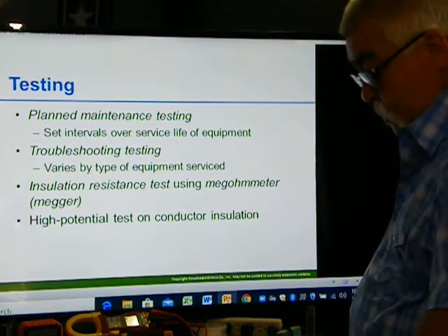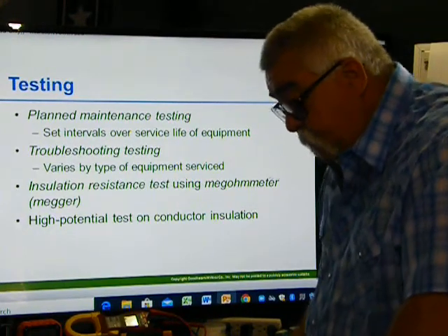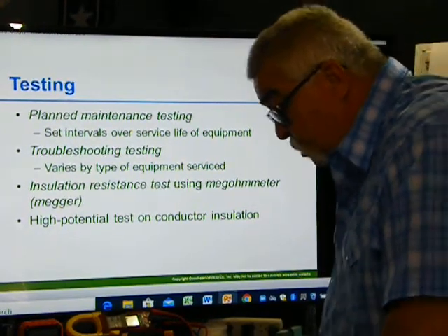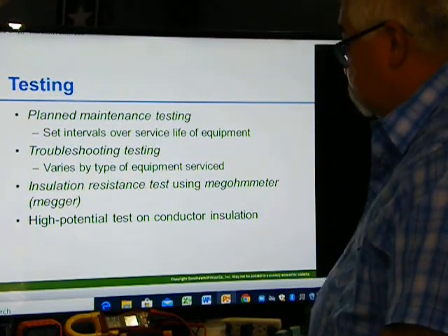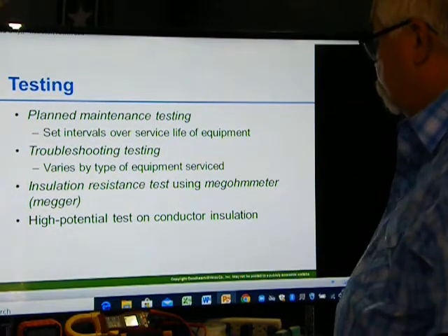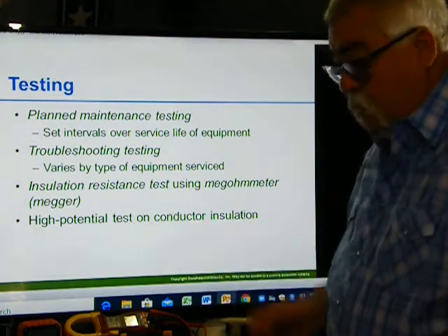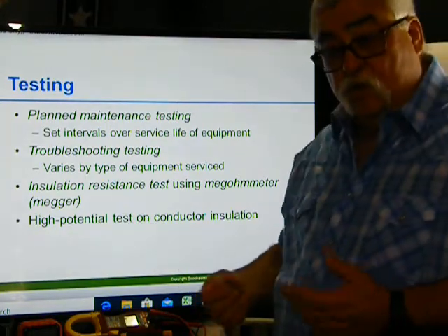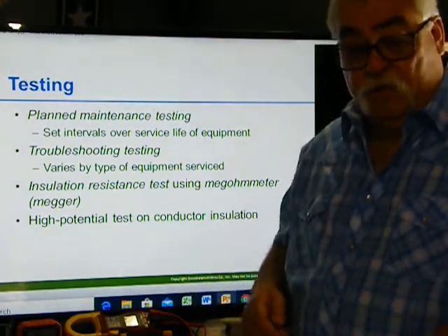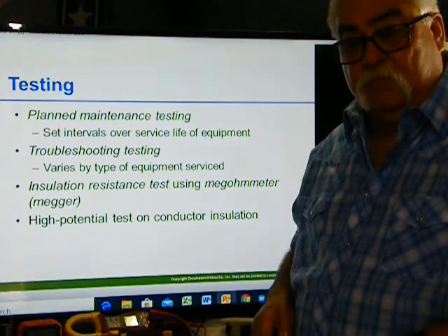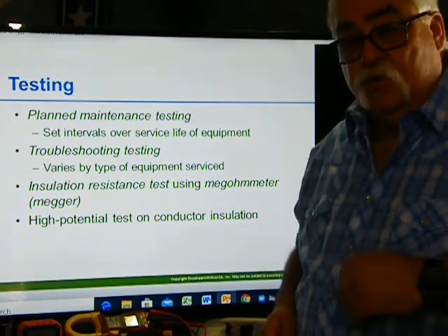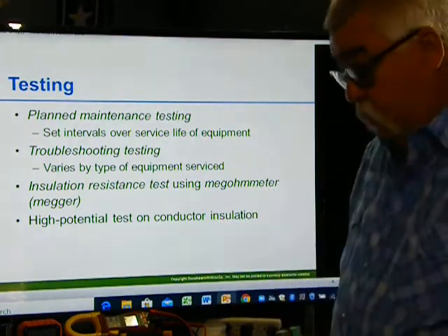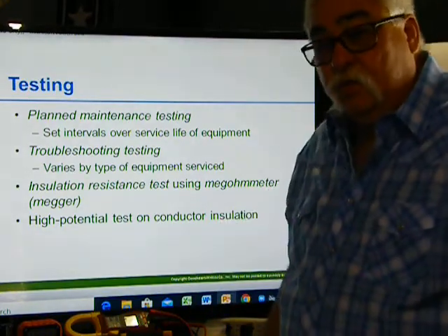Insulation. So it says some of the different troubleshooting testing. Insulation resistance testing uses a megohmmeter or a megger, and it's a special tool. You put it on, and you can do it on the motors. Sometimes it has a battery, it's electronic, you hit the button and it sends a signal and gives you a reading. The other is a crank one. I showed you all the videos in class when we were talking about tools.